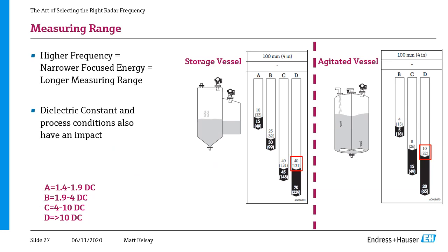This shows the influence of dielectric. Down in the bottom left, you see what those A, B, C, and D ranges are. And then in the chart, what you're looking at here is the number that's in parentheses. That's the measuring range in feet. So in a storage vessel where there's not much going on, no turbulence or anything, with that A group, very low dielectric, we are able to measure 32 feet away. But if you go up to a high dielectric, so if you had water in that same tank, now we're able to measure 131 feet away. Again, that's just because that higher dielectric is going to reflect more of that radar signal back up.